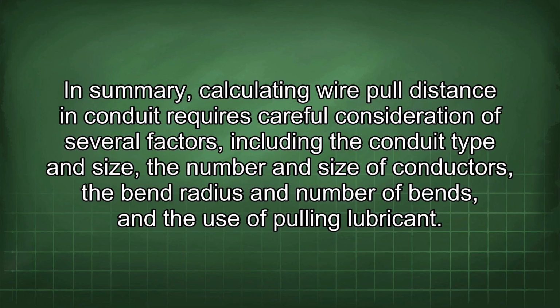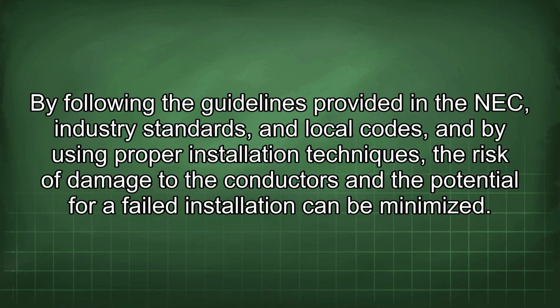In summary, calculating wire pull distance in conduit requires careful consideration of several factors, including the conduit type and size, the number and size of conductors, the bend radius and number of bends, and the use of pulling lubricant. By following the guidelines provided in the NEC, industry standards, and local codes, and by using proper installation techniques, the risk of damage to the conductors and the potential for failed installation can be minimized.